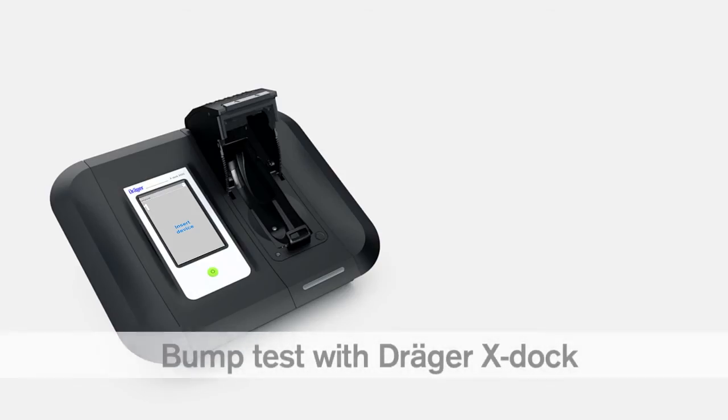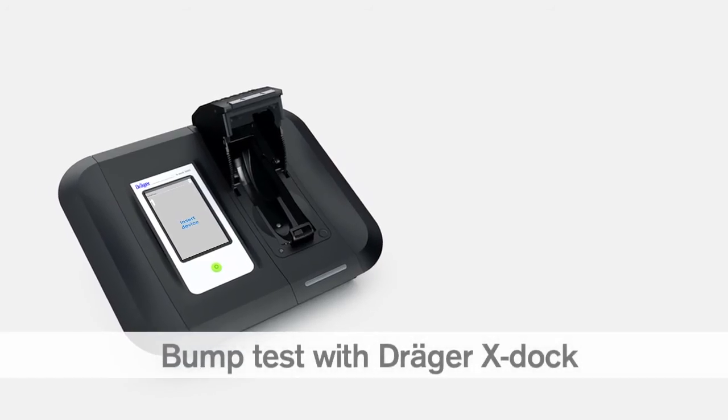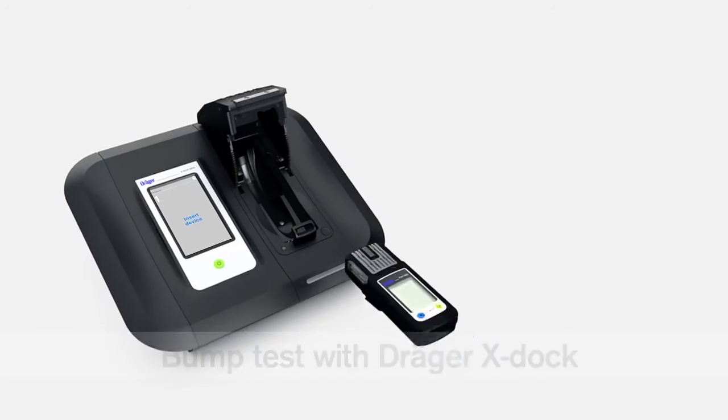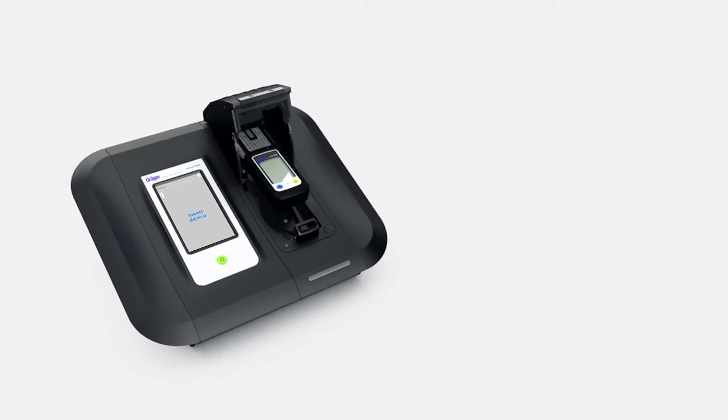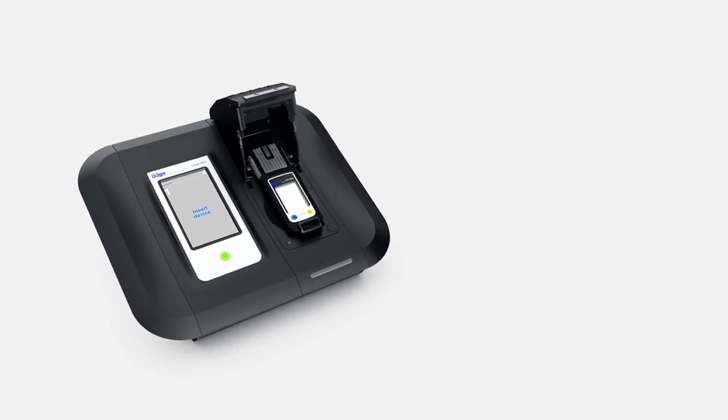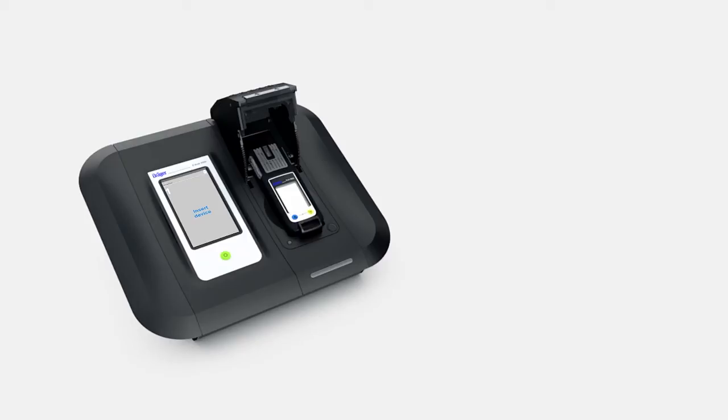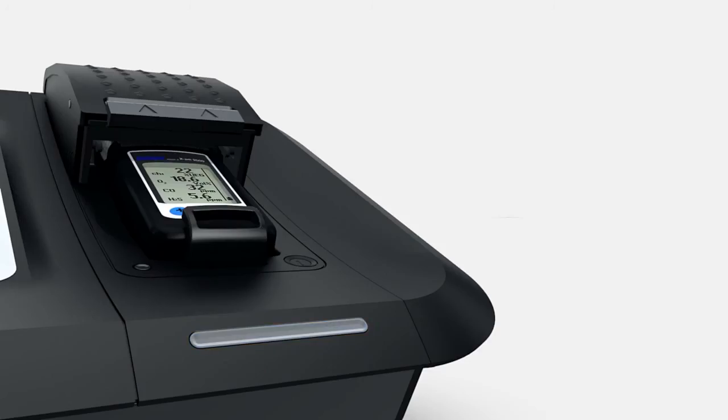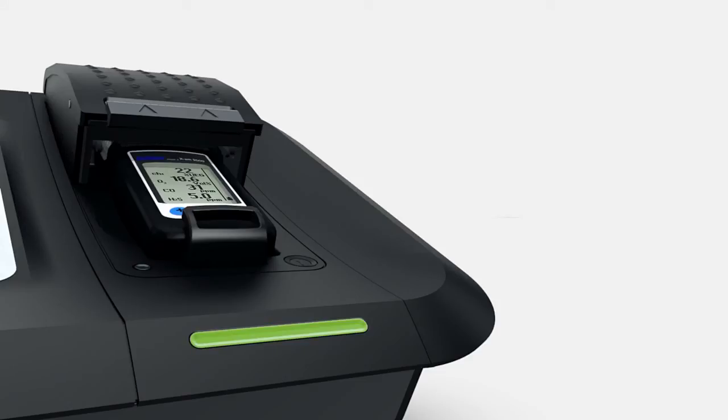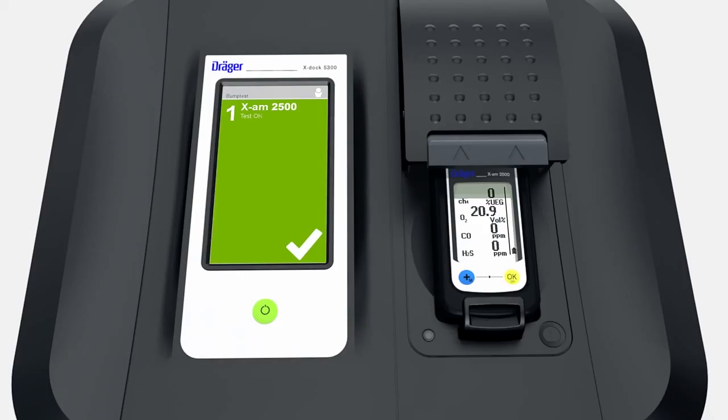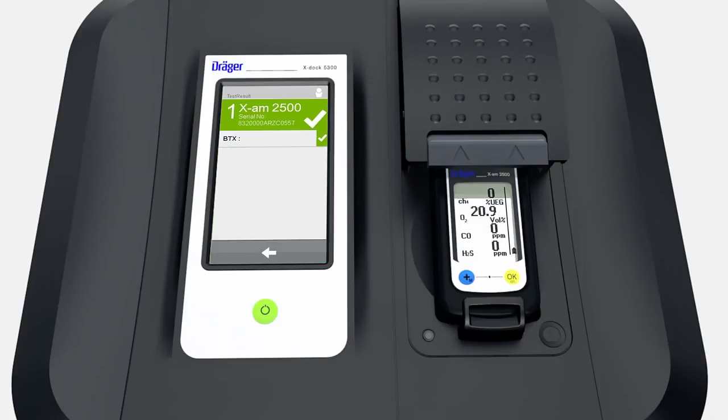You can also carry out a bump test with the Dräger X-dock station. Place an instrument inside the module. When you do so for the very first time, the Dräger X-dock recognizes the device and logs it in its integrated database. The LED strip flashes blue. When the LED changes to green, the test has been completed successfully. The X-dock screen also turns green. Touch it to obtain additional information on the test results.